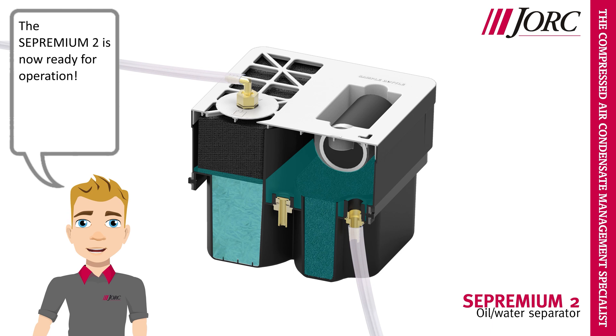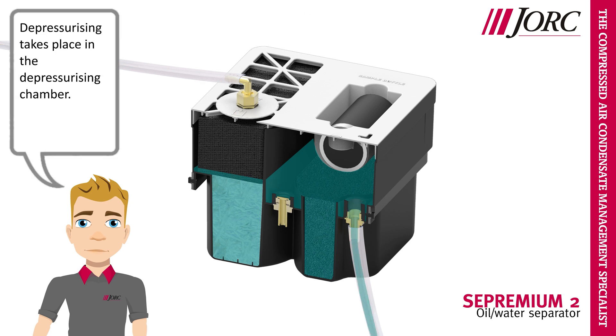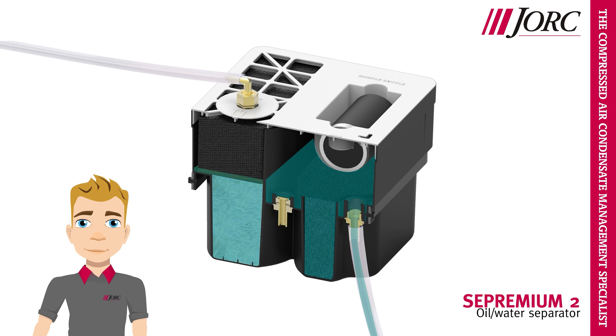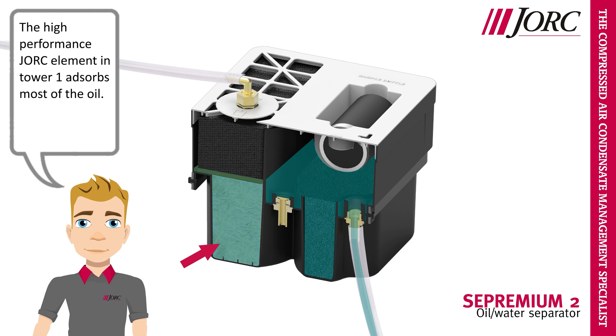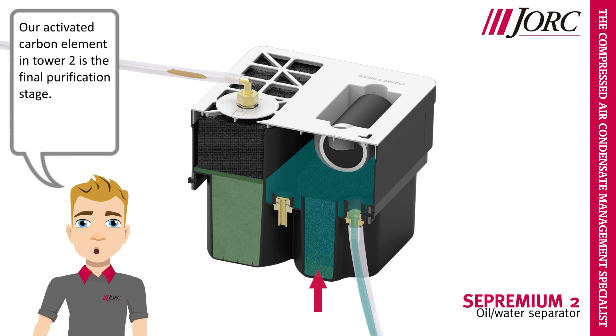The Sepremium II is now ready for operation. Condensate starts to enter the Sepremium II. Depressurizing takes place in the depressurizing chamber. The high performance JORC element in Tower 1 adsorbs most of the oil. Our activated carbon element in Tower 2 is the final purification stage.